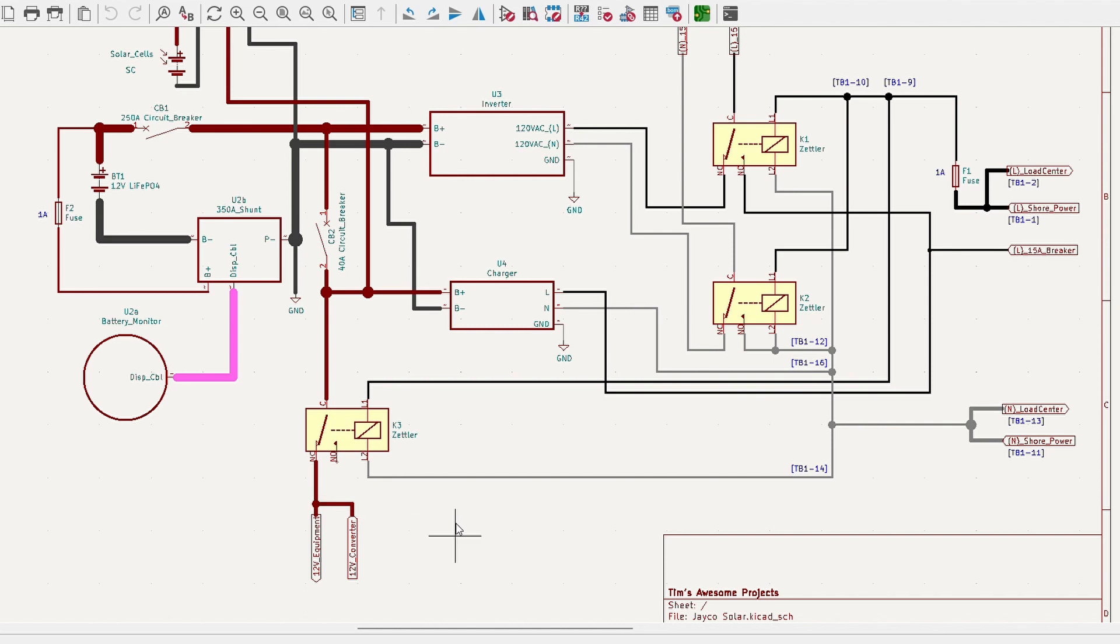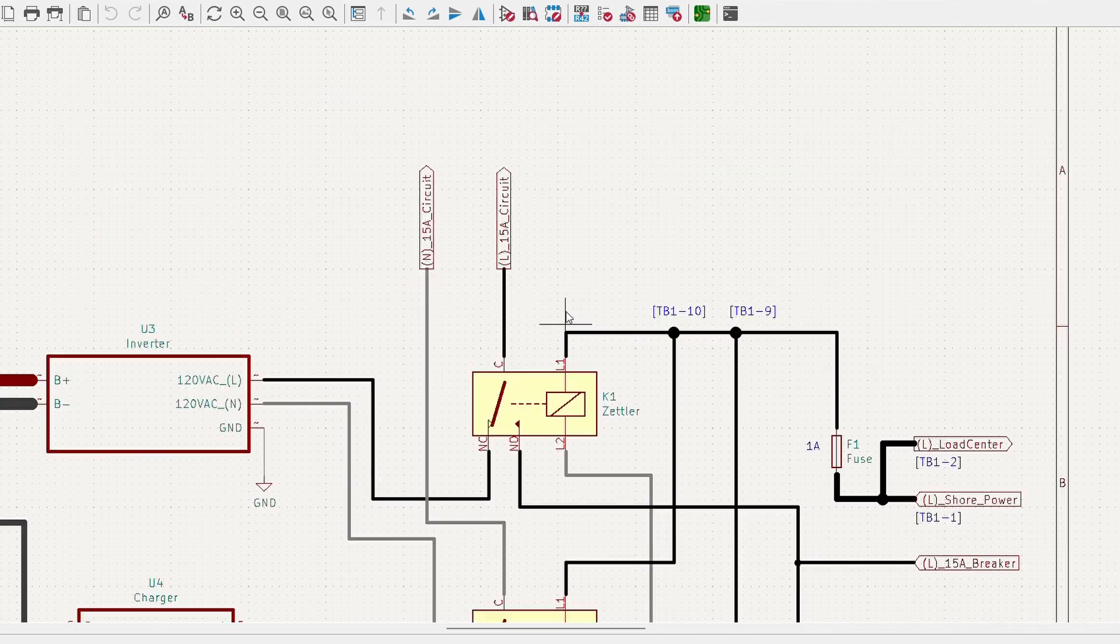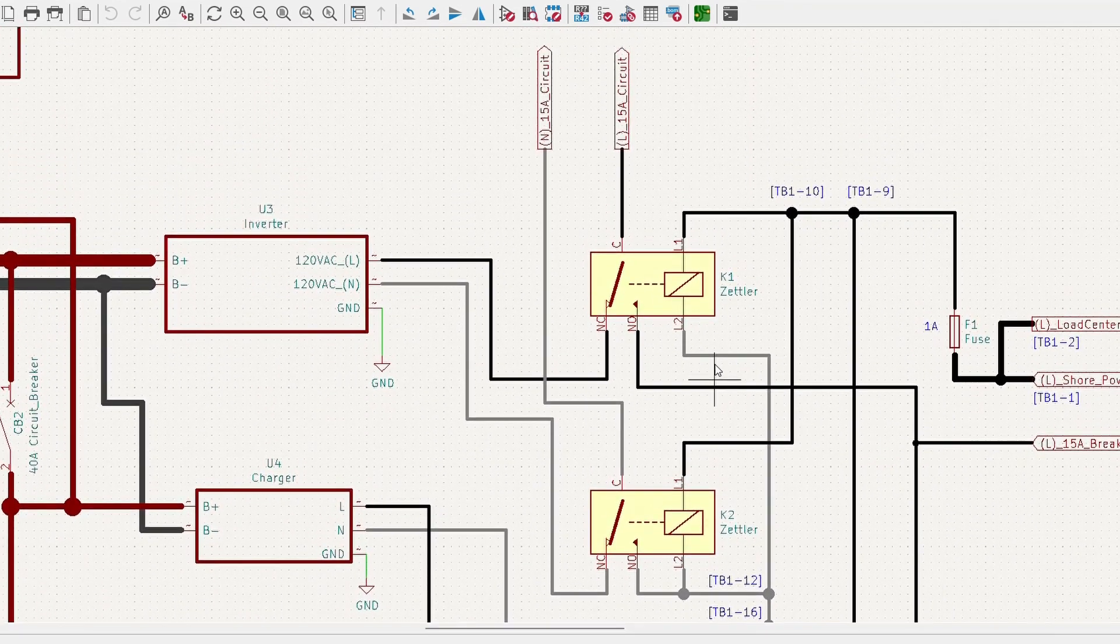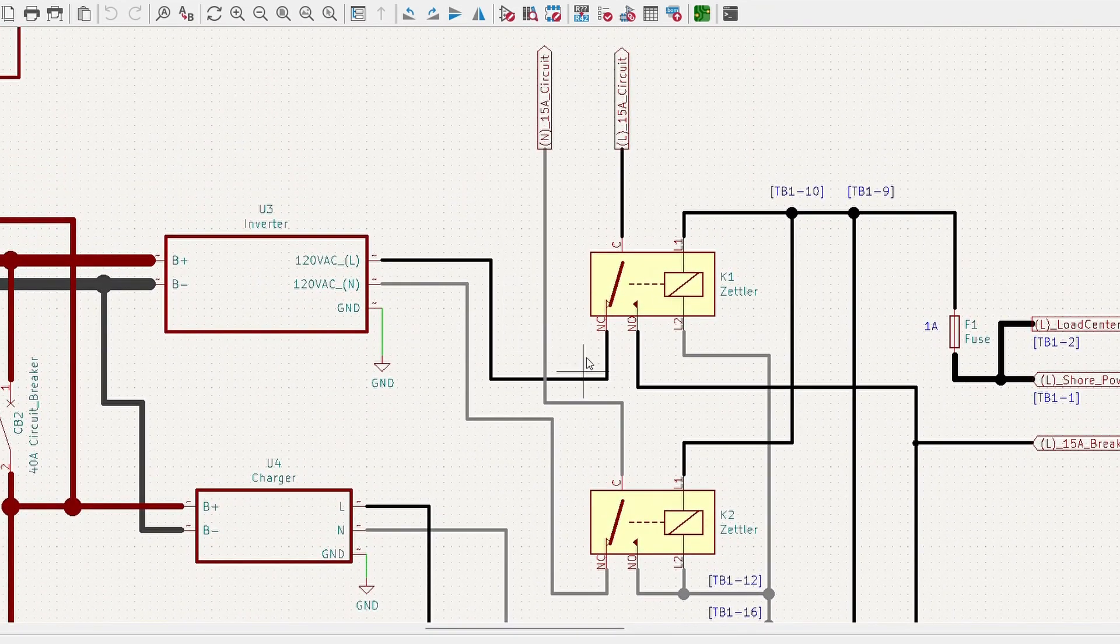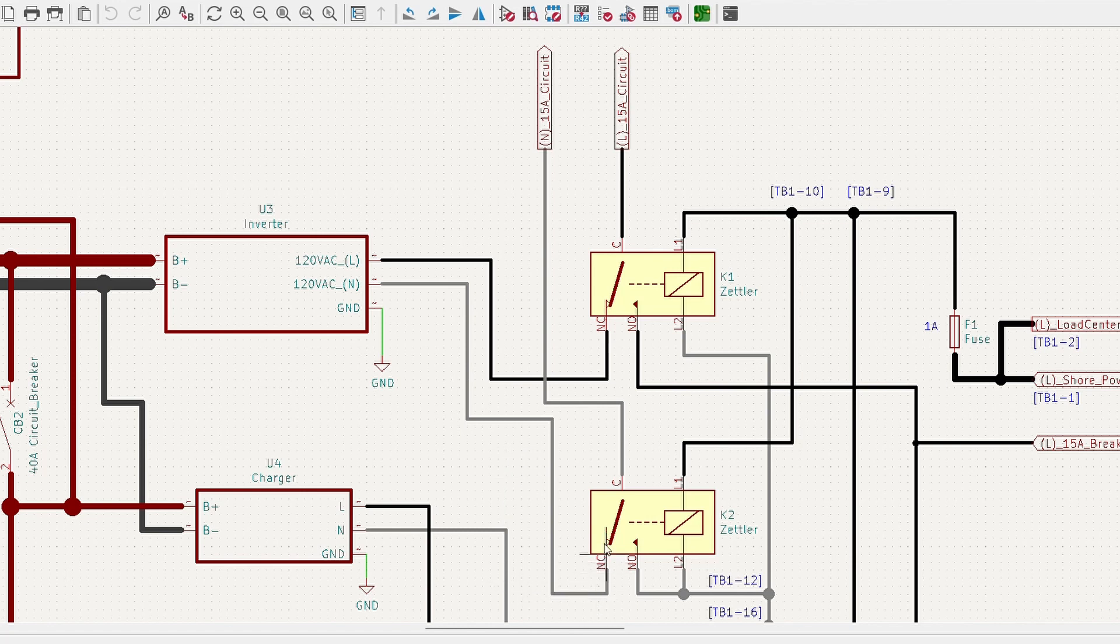Okay, so now going back, looking at the 120-volt circuitry, coming off of our inverter, if our inverter is turned on, we'll generate 120 volts, so we'll have a line and a neutral. The line will go through relay K1, which is the normally closed terminal, will then feed. So our 120-volt will jump to our 15-amp circuits that are connected to the inverter-protected circuitry. And we do the same thing for the neutral. So the neutral then also goes through the normally closed contact to the neutral side of our branch circuit.